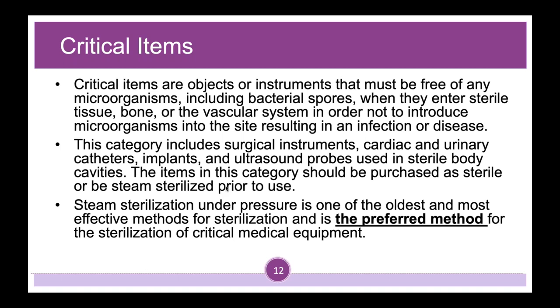Steam sterilization under pressure is one of the oldest and most effective methods for sterilization, and is the preferred method for the sterilization of critical medical equipment. It is the preferred method. The thing about steam sterilization that you have to remember, and this is why that chart we were looking at before is very important...